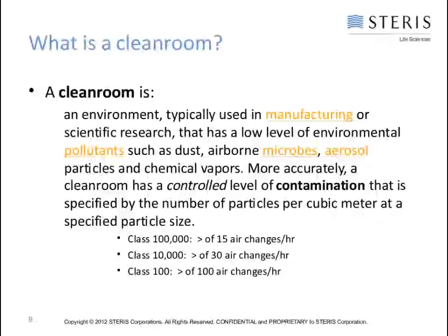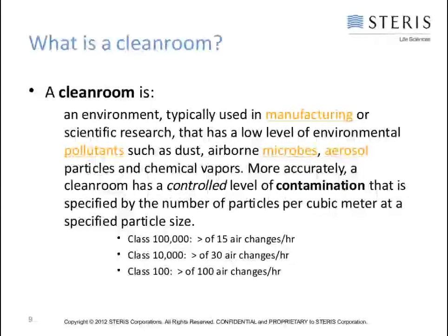Temperature and relative humidity control is vital. All facilities should maintain 30 to 60 percent relative humidity 24 hours a day. For class 100,000 clean rooms, we see greater than 15 air changes per hour. Class 10,000 requires greater than 30 air changes per hour. Class 100 requires greater than 100 air changes per hour.